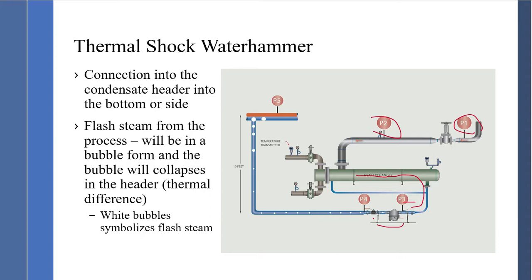To get the condensate temperature down to the lower pressure, a percentage is released as flash steam. The flash steam exists as bubbles carried along the condensate line. As pressure is reduced, the bubble increases in size. When the bubble enters below the condensate level in a condensate line, it collapses and you hear ping, ping, ping. With higher condensate flow, the bubble is much larger and you hear bang, bang, bang.